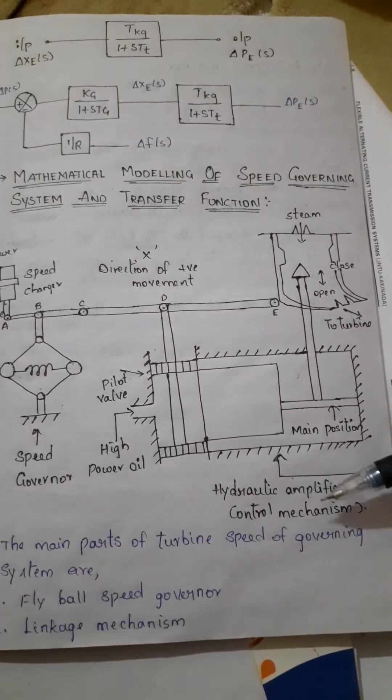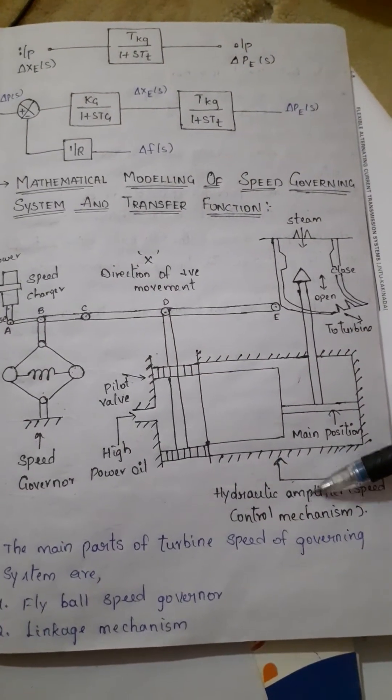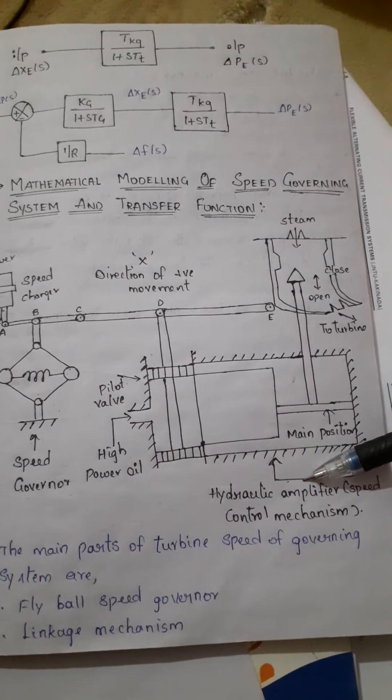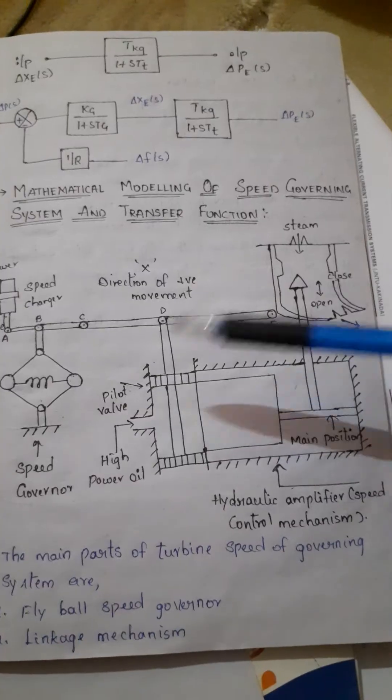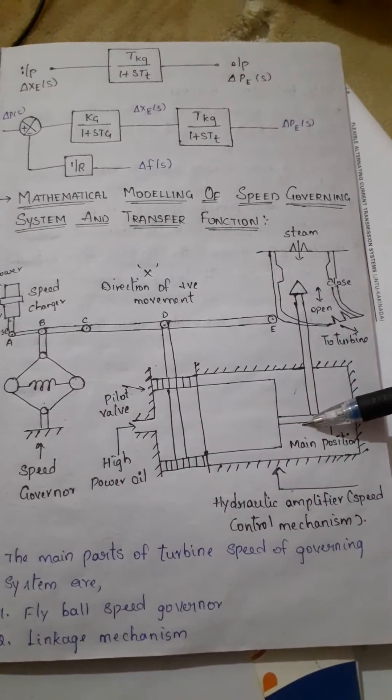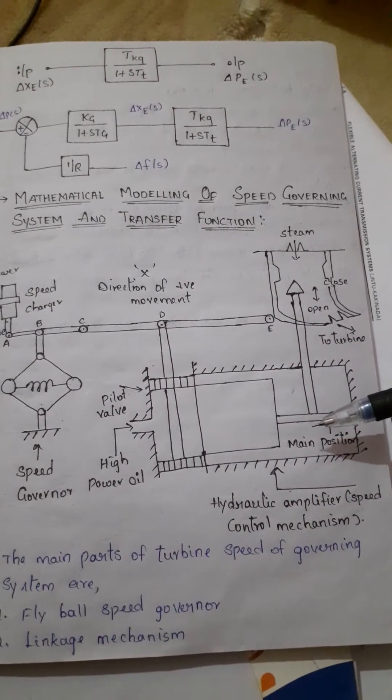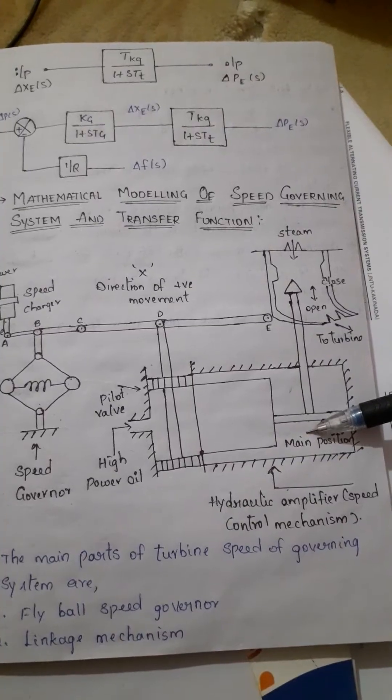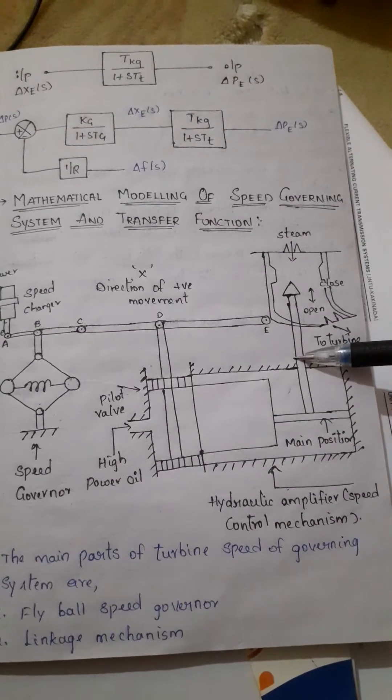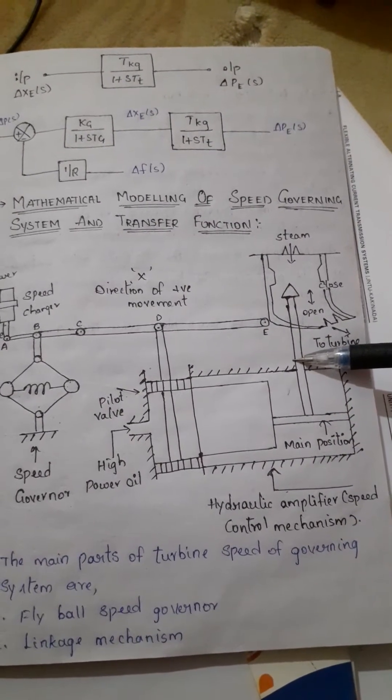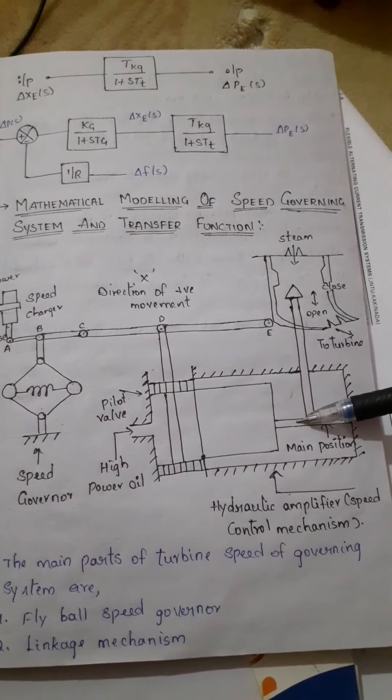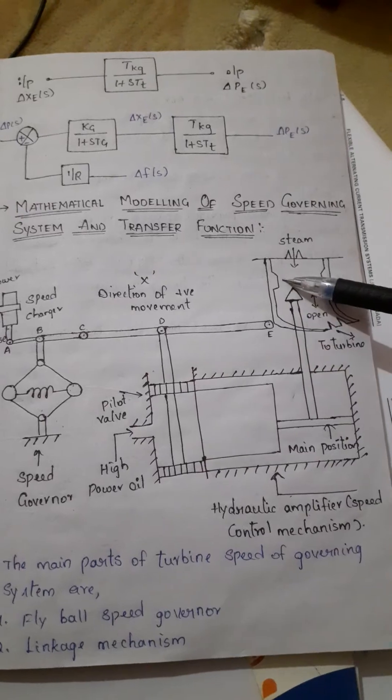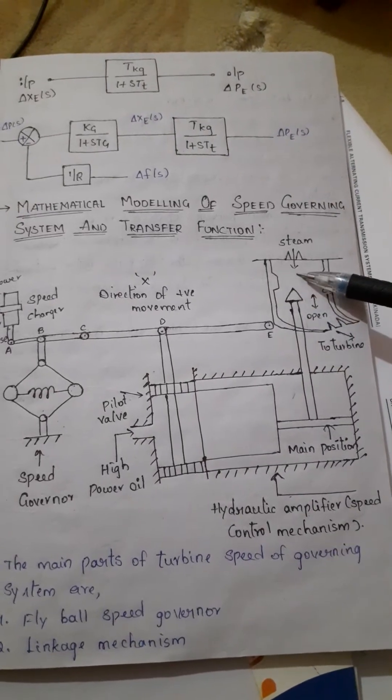Next is the hydraulic amplifier. In hydraulic amplifier there are two main parts: one is the pilot valve and another one is the main piston. The lower pilot valve movement is converted into higher level piston valve movement. This is necessary in order to open or close the steam valve against high pressure.